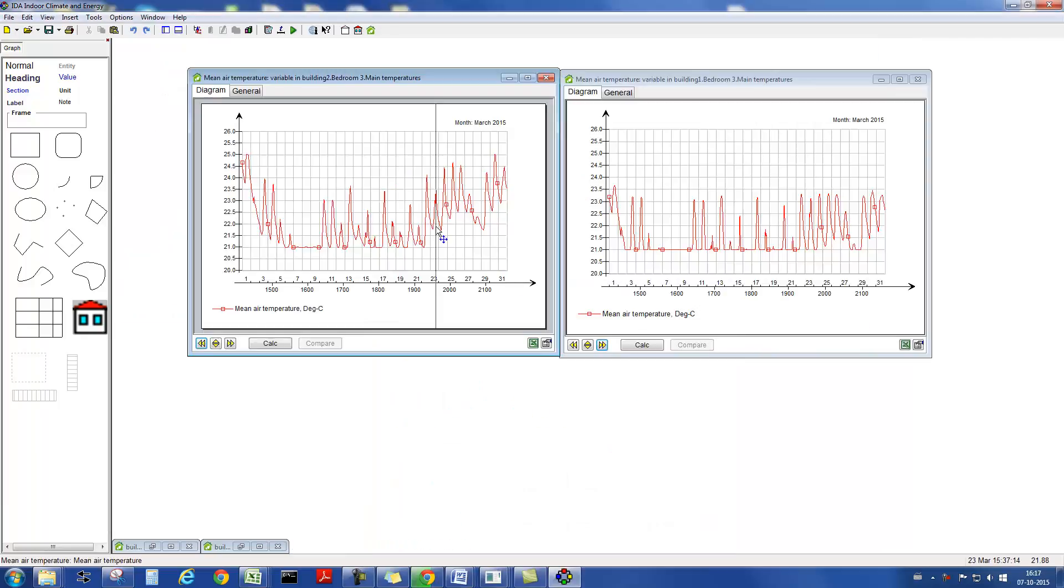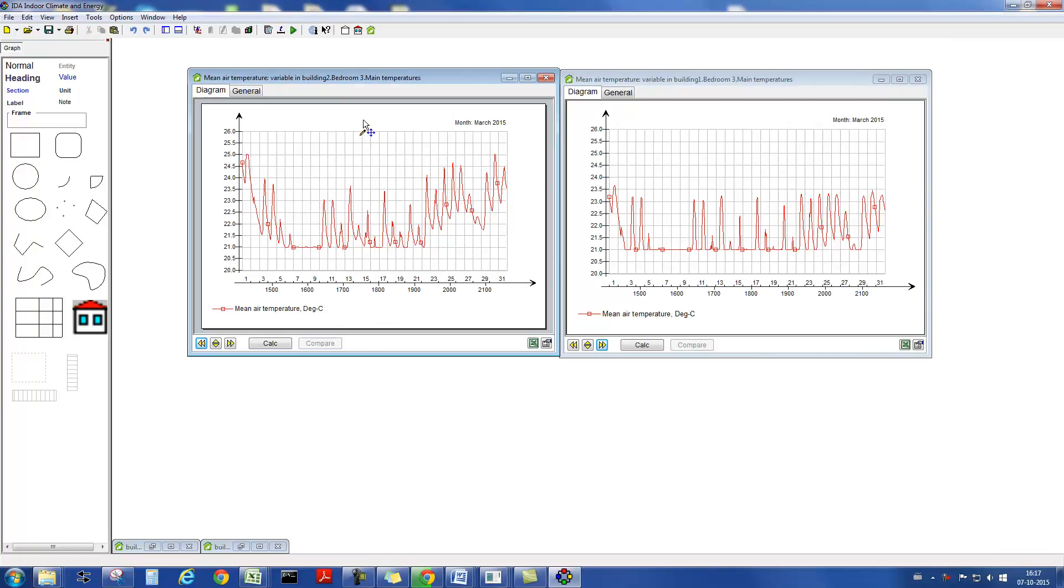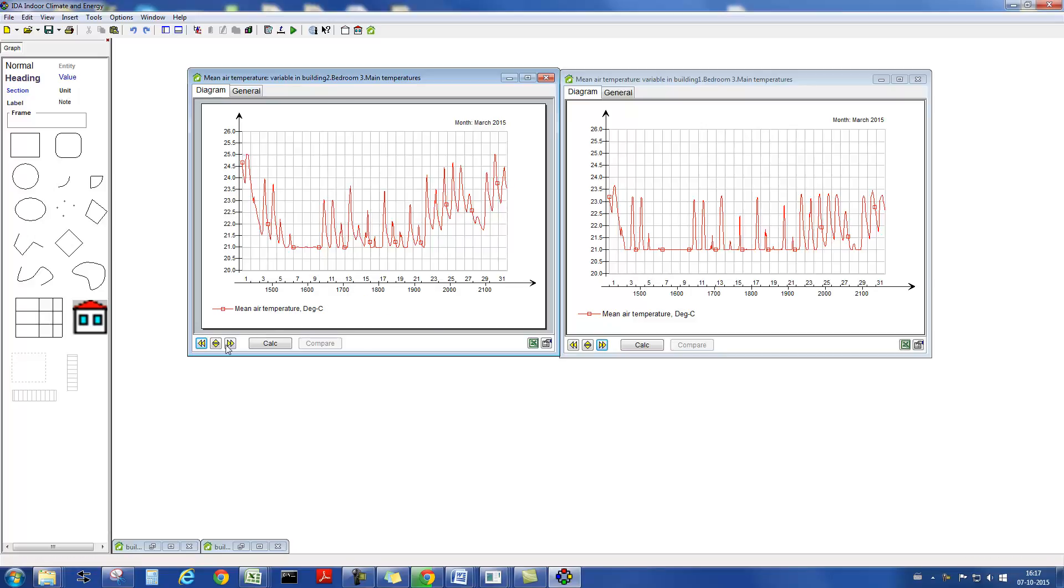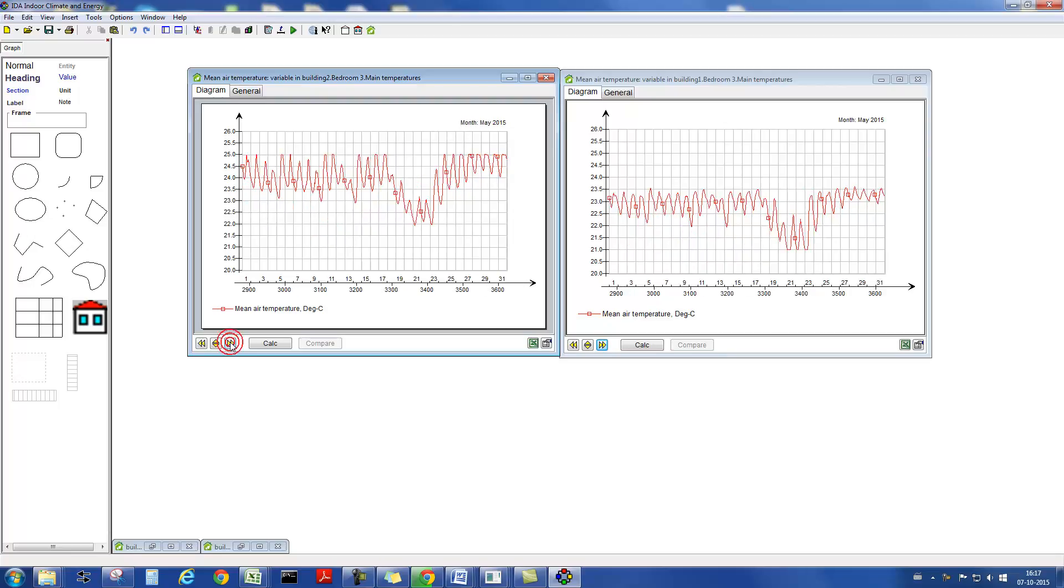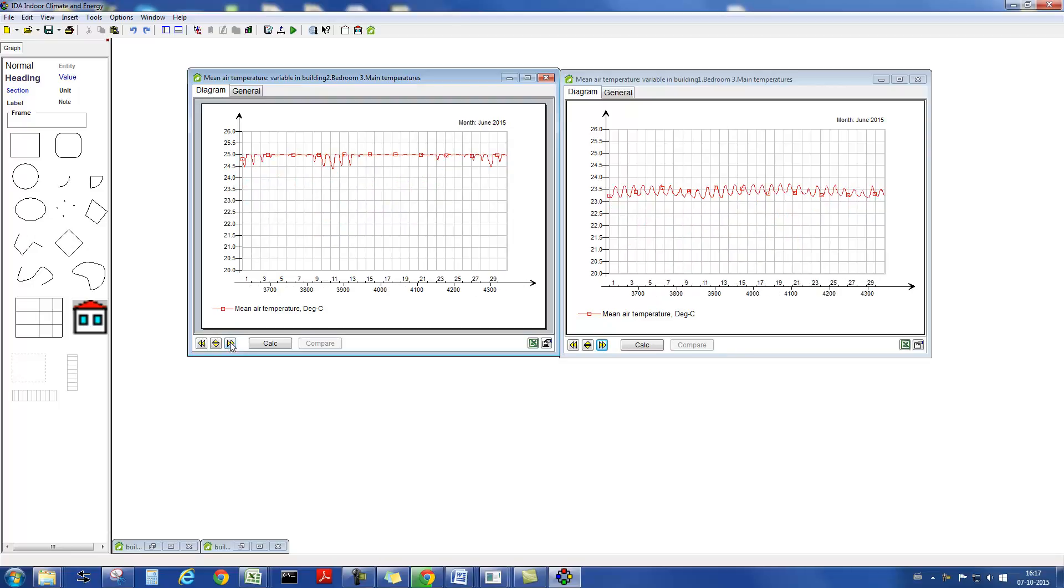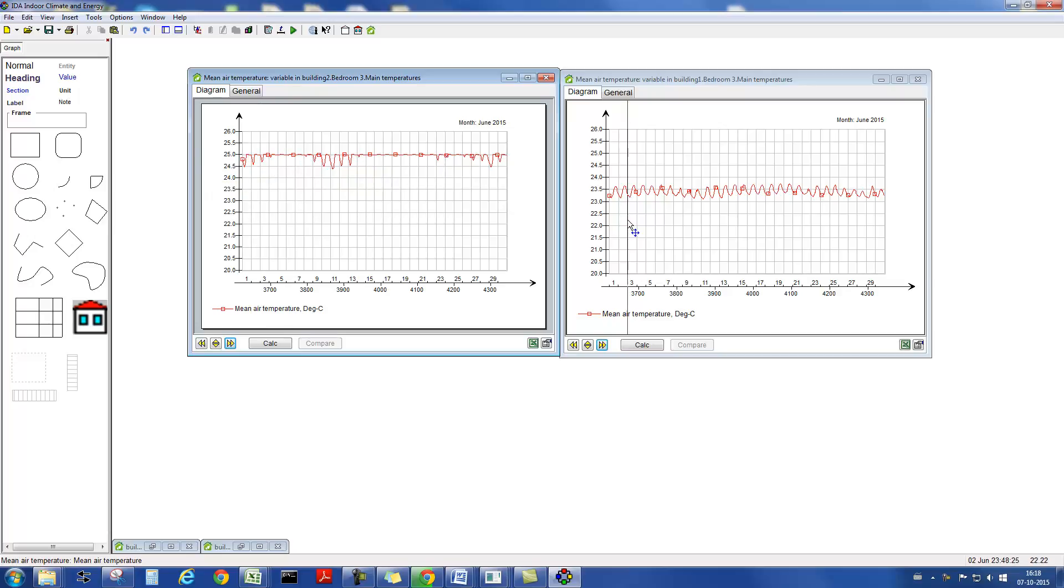We can also compare the temperatures in the zone with constant air flow, shown on the left, to one with a variable air flow. There is a greater temperature variation with a constant air volume system, and over the year, also a greater increase of the air temperature in this zone. Note that the zone contains a local cooling element, which is turned on at 25 degrees C air temperature. Otherwise, the increase would be even more significant.